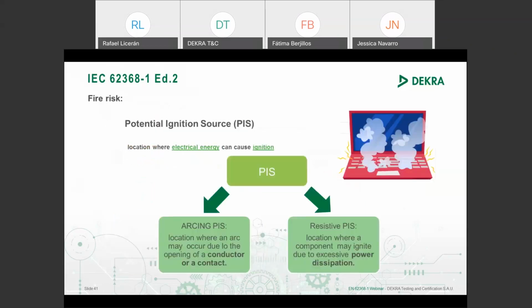We have to take into account, in addition to the energy in a circuit, the potential location or point in the equipment that could be a potential ignition source that causes a flame. In this way, I have two kinds of PIS: arcing PIS or resistive PIS. Arcing PIS is produced when a contact occurs and I have a high voltage. And a resistive PIS is produced only by dissipation of power.